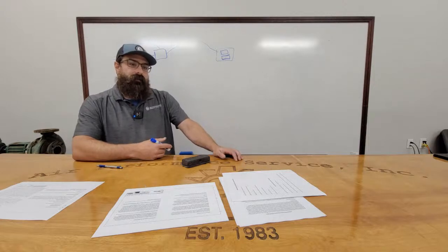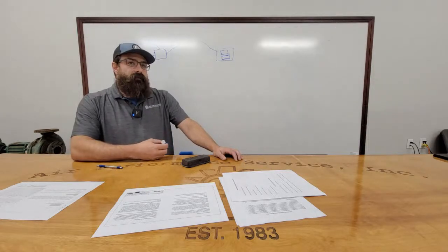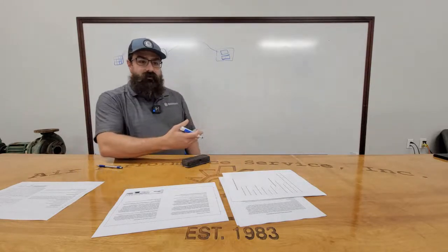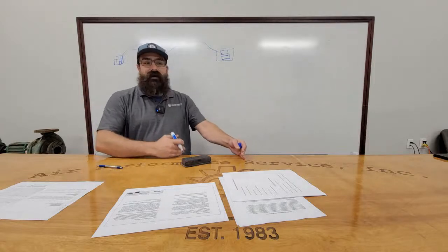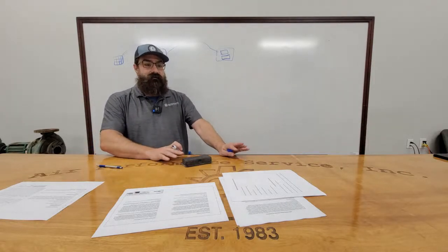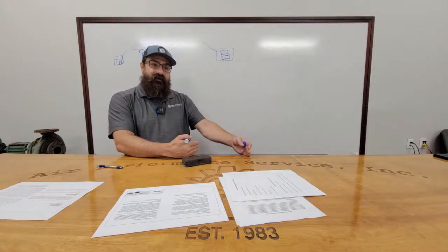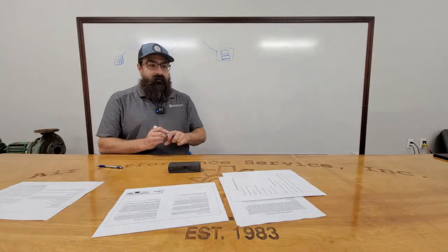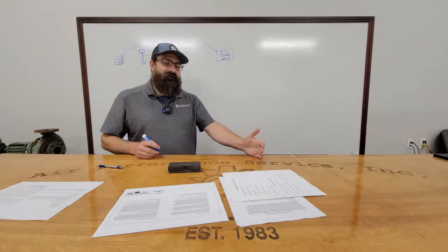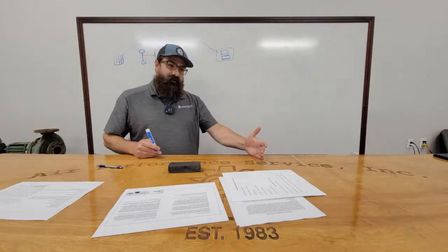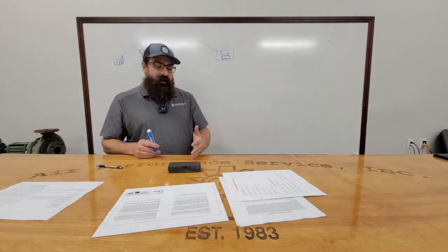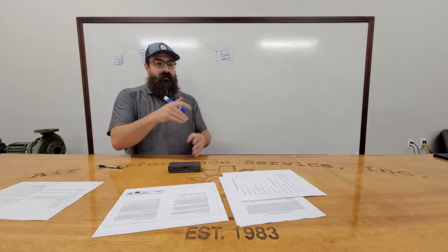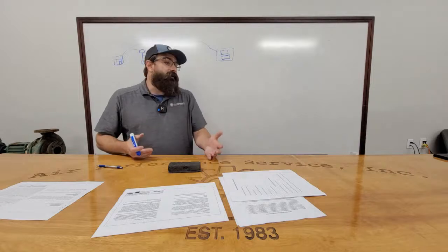Well, that sounds more efficient since you wouldn't short cycle your equipment either. Well, it is, but it isn't, because the load is based on deviation from set point, right? If you've got a global set point and every single box is set to 85 degrees, then you can do temperature all day. But if you change that unoccupied set point in every box or half the boxes, well, that 85 degree set point is no longer valid. You would have to adjust that set point. Whereas if you have load based, you can change all the temperature set points in the boxes all you want. All you care about is the load of the equipment. So that's our preferred way to do it.